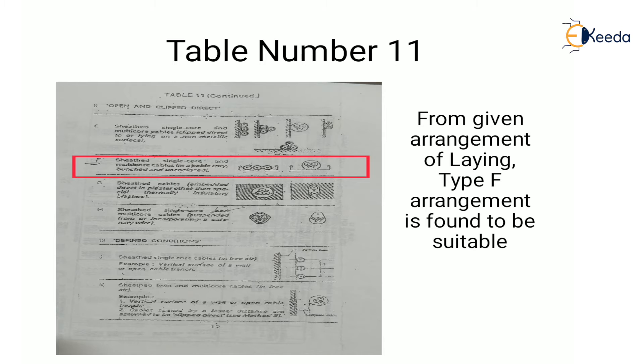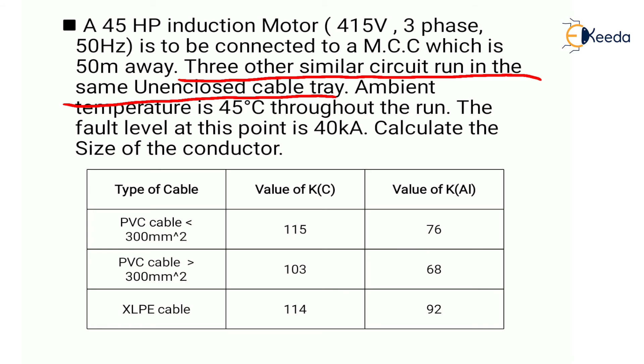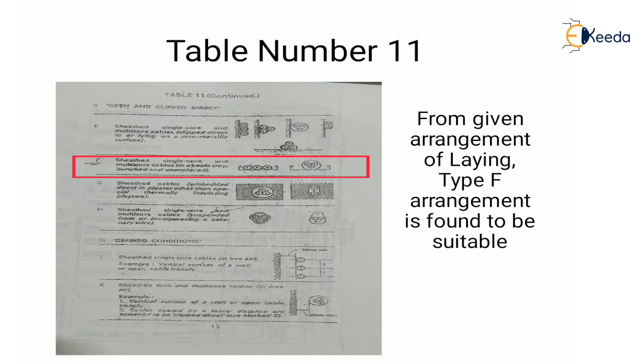First, we find the arrangement for the cable. From Table 11, we select a suitable arrangement of laying. Since three other similar circuits run in the same unenclosed cable tray, we match this with the table. There are arrangements A, B, C, D, E, F, G and so on. Based on our requirement, the Type F arrangement is found to be suitable.